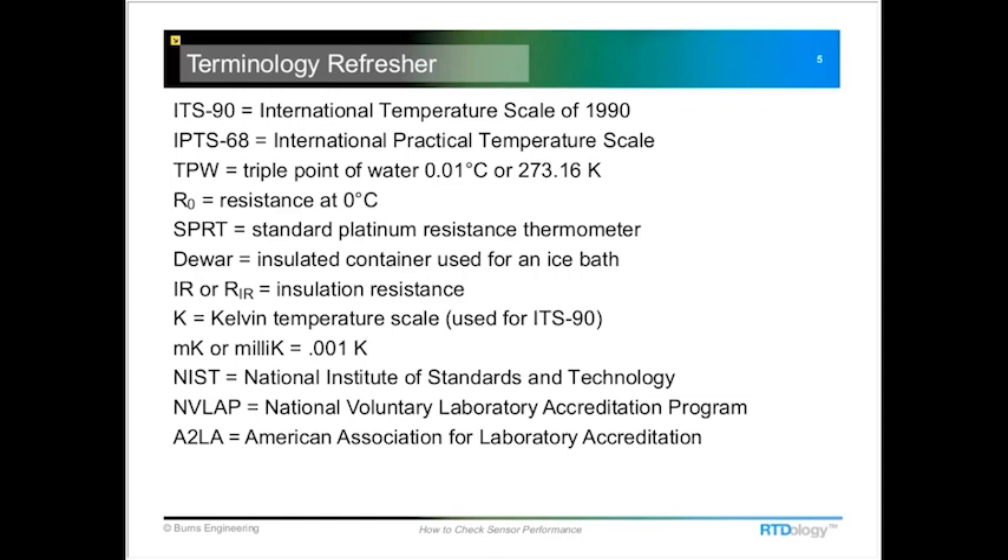Here is some of the jargon and terminology we encounter when talking about calibration or verification of RTDs. The ones we'll hear most today are R0, which is resistance at zero degrees C, and Dewar, which is just an insulated container used for ice baths. Then there's insulation resistance — often called IR or written as R-sub-IR — which is one of the most important checks that most people don't perform on RTDs, and I want to show why it's important today.